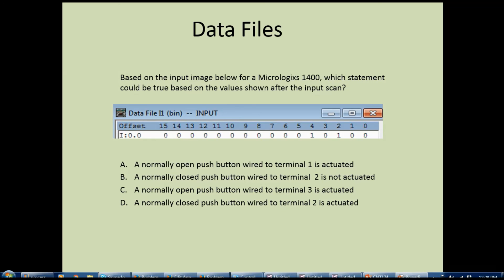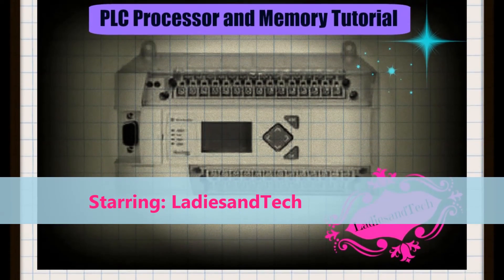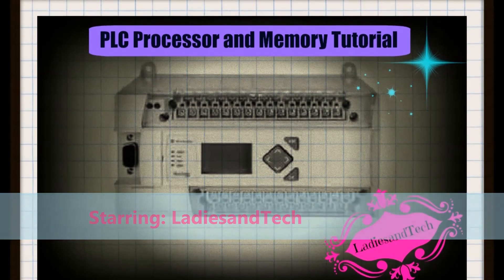Statement B: a normally closed push button wired to terminal 2, not actuated. A normally closed push button when not actuated gives a logic level of one. Looking at bit two in the input image, it is a logic level of one - so B is a true statement. Statement C: a normally open push button wired to terminal 3 is actuated. When actuated it should give a logic level of one, but looking at bit three in the input image it is a logic level of zero - so C is false. Statement D: a normally closed push button wired to terminal 2 is actuated. A normally closed push button that is actuated gives a logic level of zero, but bit two shows a logic level of one - so D is false. That concludes this tutorial.